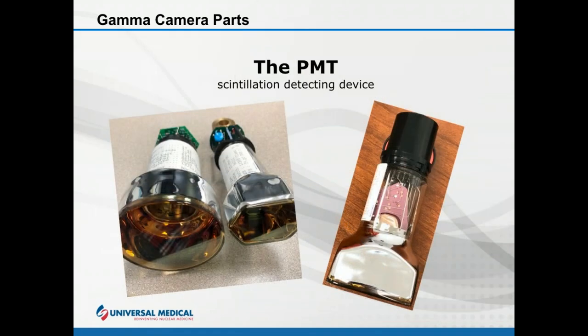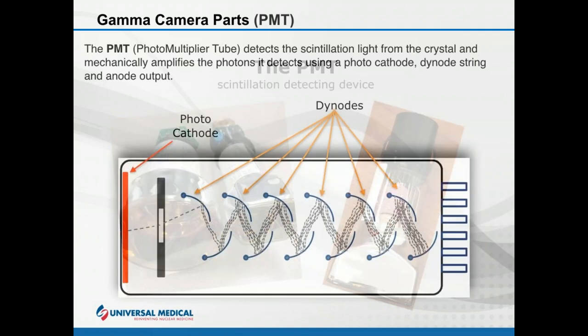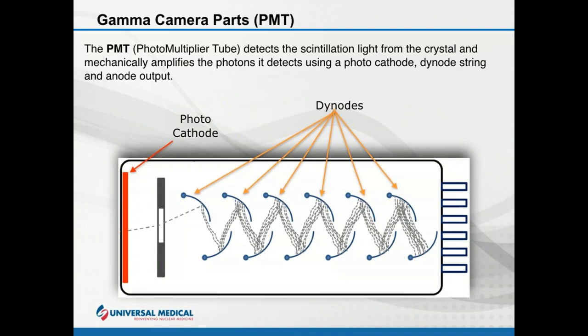Having made it through the collimator and impacted the crystal causing scintillations, we hit photomultiplier tubes. PMTs come in many shapes and sizes — circular, square, octagon — depending on the manufacturer. The basic principle of every photomultiplier tube is: a photocathode goes through a focusing grid, runs through stages of dynodes, and goes to an anode.